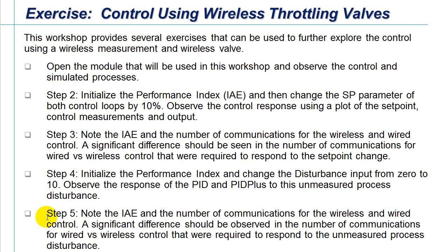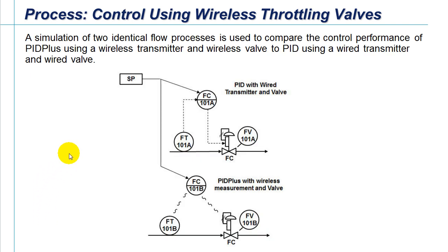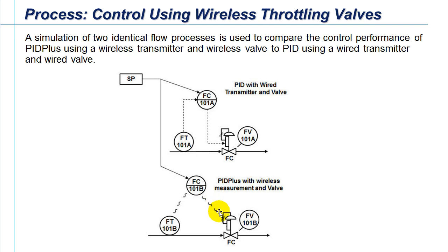For this workshop, we're simulating two flow processes — one controlled by wired and one controlled wirelessly. The process that has wired input is using PID to adjust the wired output. PID Plus is used for control using a wireless flow measurement, and its output is going wirelessly to a throttling valve, so both the input and output for the PID Plus are wireless.